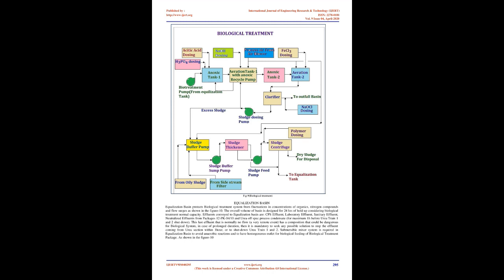Continuous return of activated sludge to the aeration tank is provided to maintain the required MLSS in the aeration tank. In the process, excess sludge built up in the clarifier is taken out regularly from the system into the sludge buffer sump. The settled sludge concentration in the clarifier is 0.6 to 0.7%. The clarifier is equipped with a rake mechanism which operates continuously. Clarified water flows by gravity to the outfall basin.